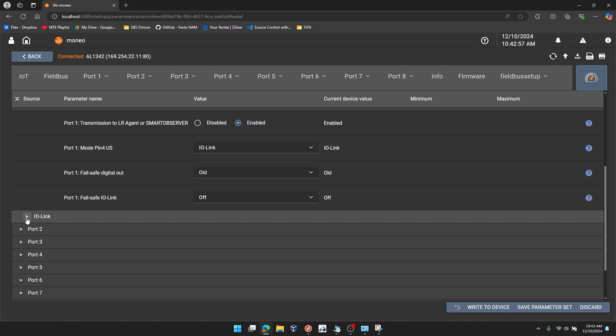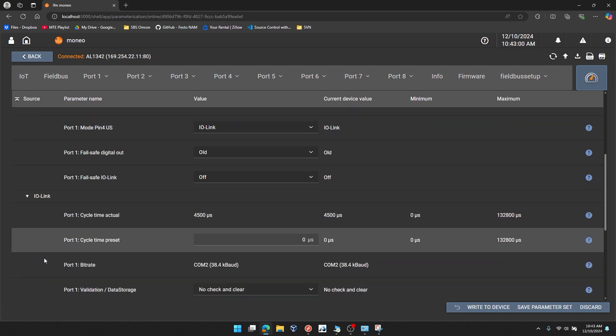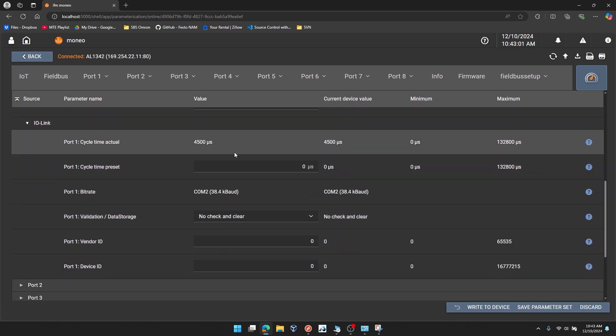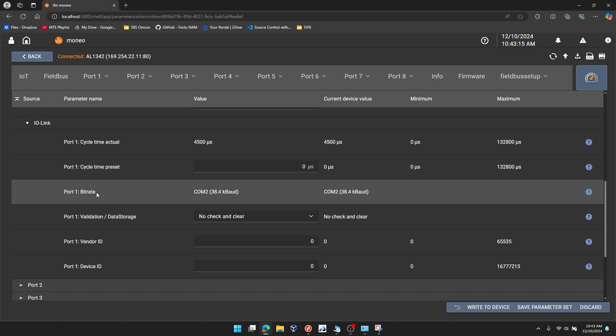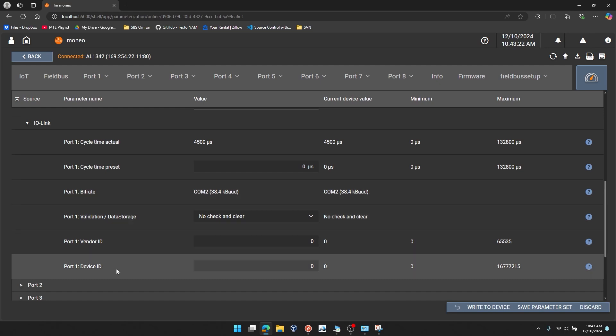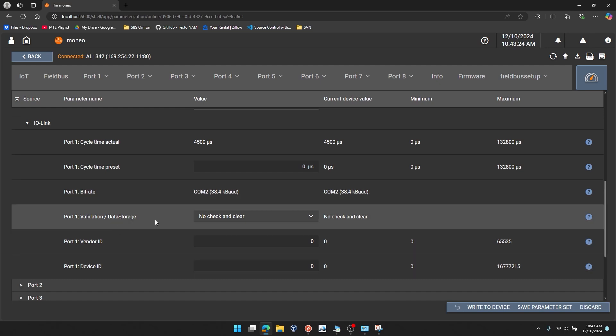At the bottom of port 1, there's another section titled IO-Link. Expand that. Within this section, you can see some of the defaults for that IO-Link port. You can see the cycle time actual that's detected. The cycle time preset if you want to do a fixed value. If it's value 0, this will auto-negotiate. So I would recommend leaving this as 0. The achieved bit rate, COM 1, 2, or 3. And you can see it's detecting COM 2 currently.